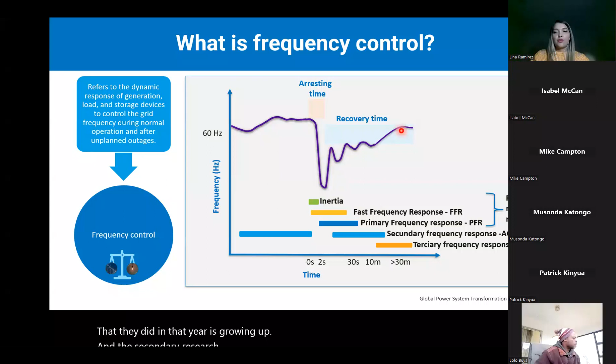Inertia, I think this is really basic. This is the kinetic energy stored in the rotating mass of synchronous machines. Synchronous condensers, synchronous generators, and motor loads can provide that inertia. So load is also important to mention here. This stored energy is important to the power system when a large generation fails or a load trips, to maintain the balance in the first seconds, avoiding the nadir touching the under frequency relays, or over frequency relays in some cases.